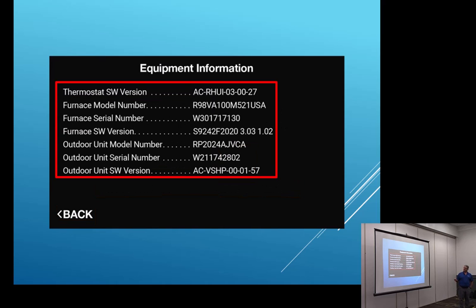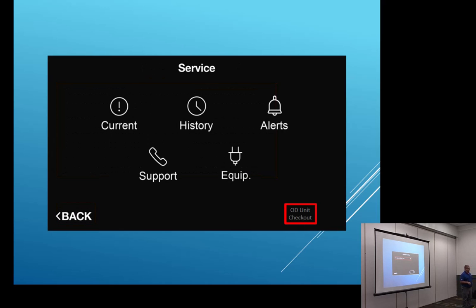Equipment. I'm going to want a picture of this equipment screen. It's going to give my furnace or air handler model and serial number, outdoor model and serial number. And it's also going to give us thermostat, furnace, and outdoor unit software information. So if we have the wrong software or there's updated software, this could be our problem, and you can go and update the board going forward. We don't have to change memory cards or anything or have somebody come out and change it for you. We can all do it on our phone.